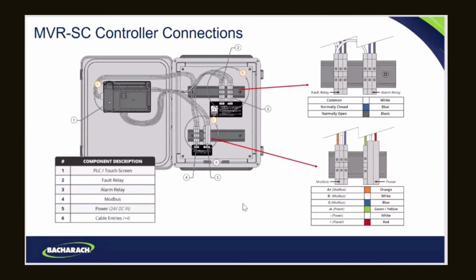You mentioned that fault relay and the alarm relay. We will tie those into the nurse call also. That way they have a general notice that we've got a problem with the system, and the other one will tell them through the patient station exactly which one it is. Right. And if you get an alarm here, it might not be a problem with an MVR. It may just be a communication issue with the Ethernet side of it. So that's a higher level for sure. Okay, cool.